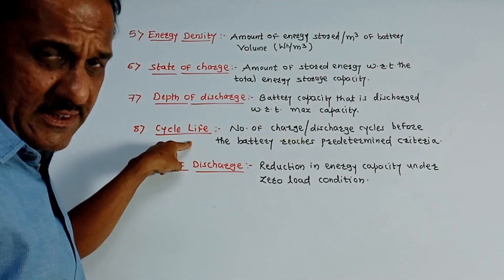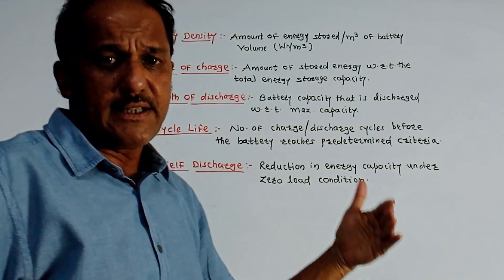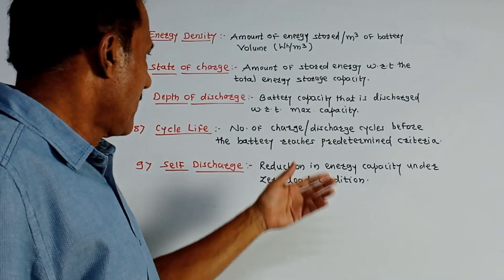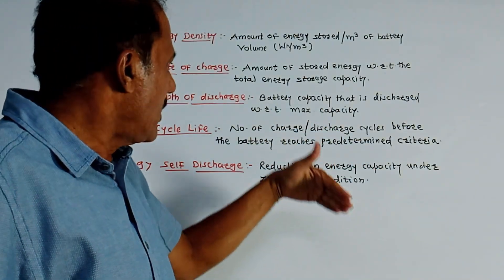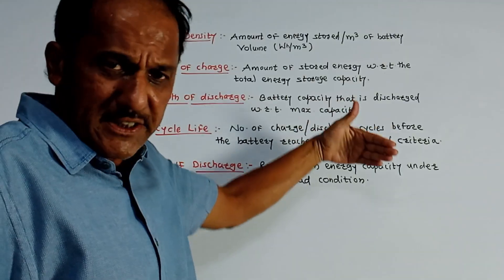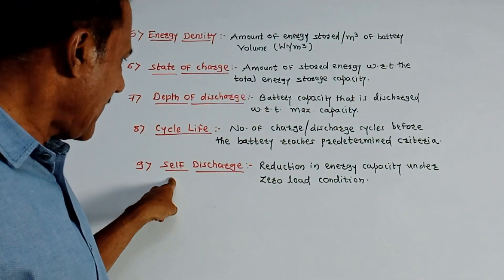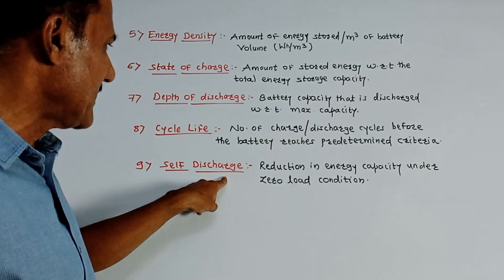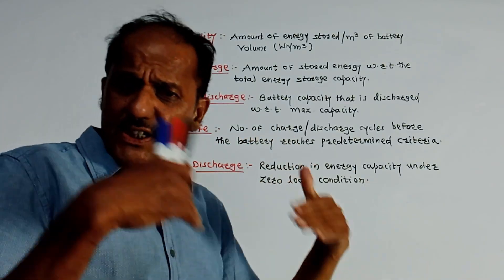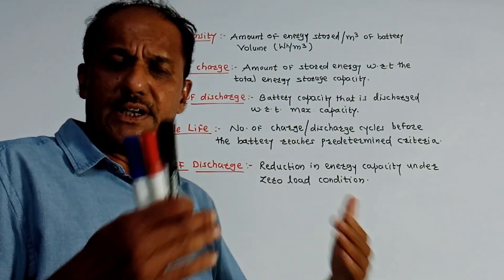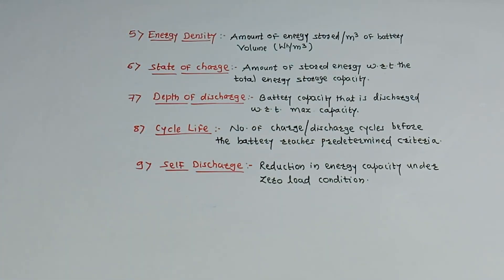Cycle life refers to how many times the battery is charged and discharged before it reaches a predetermined criterion, such as predetermined energy levels. The last parameter is self-discharge, which represents the self-discharging capacity of the battery when there is no load — that is, under zero load conditions.